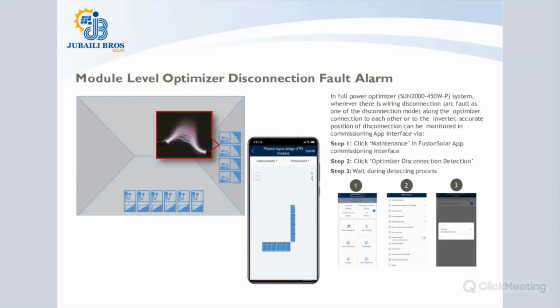So how do you do this? In the PV inverter app system, you click maintenance, and then you click optimizer disconnection detection. You wait for the system to detect, and you are able to pinpoint exactly in the system which module created the arc, where the alarm is coming from, where the fault is coming from. You are able to detect it in detail. This actually removes a lot of O&M run around the system.